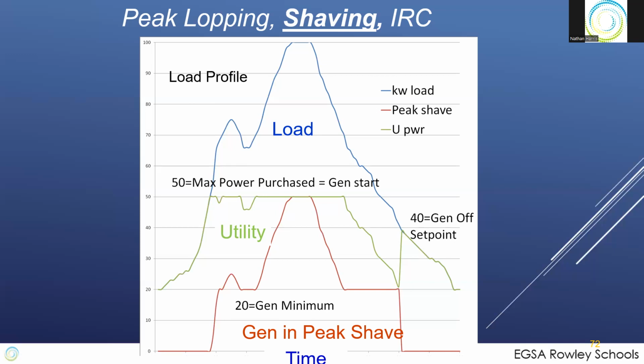They'll take on the load as we go up, and you'll see the generator in peak shave power goes up when this goes up. At this point, we came back down a little bit, but we didn't actually reduce the output of the generator. We let the utility drop down a little bit because we never want to go above 50. And so throughout the day, the generator ended up taking over the numbers.